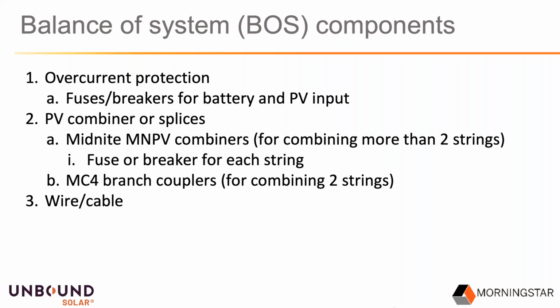If it's just 2 strings, you can use an MC4 branch coupler, which is just a plug and play. Assuming the panel has MC4 connectors, it's just a plug and play way to combine 2 strings. And then of course, wire and cable to connect the PV panels into the combiner, and then from combiner back to controller.